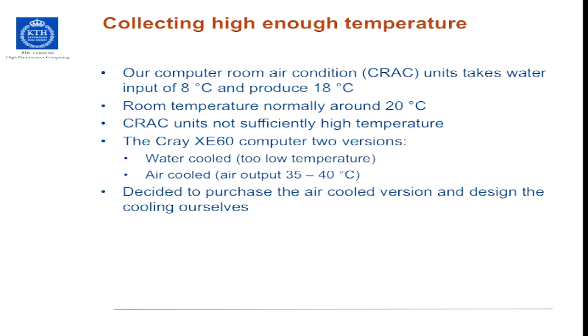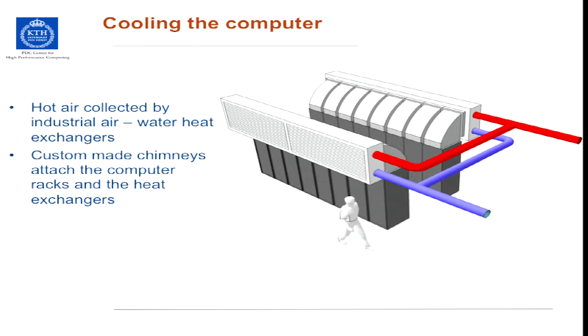So we did place industrial heat exchangers above the actual Cray. The Cray system sent out this hot air up on the upper side of the cabinets. They take in cold air from the raised floor and send it up right out in the air. So we built some chimneys and placed heat exchangers on top of the Cray. And that worked fairly well. It had worked very well for 4 years.